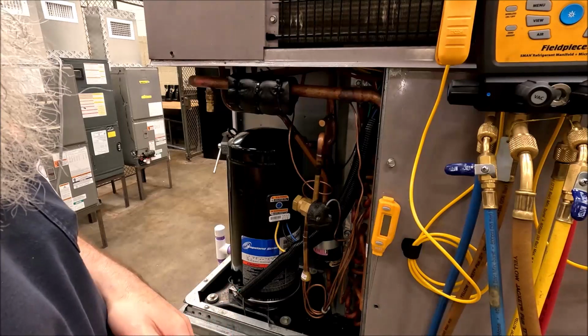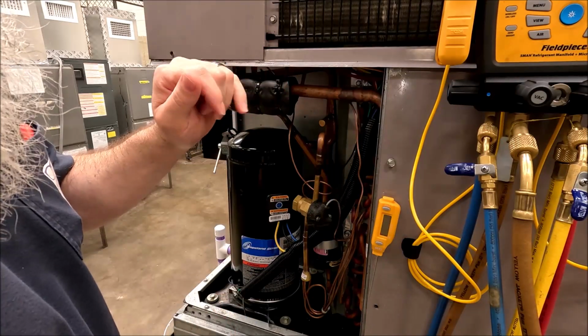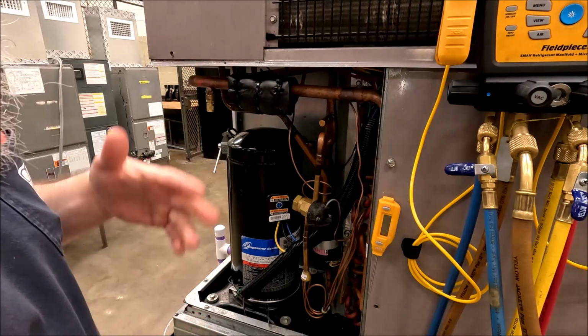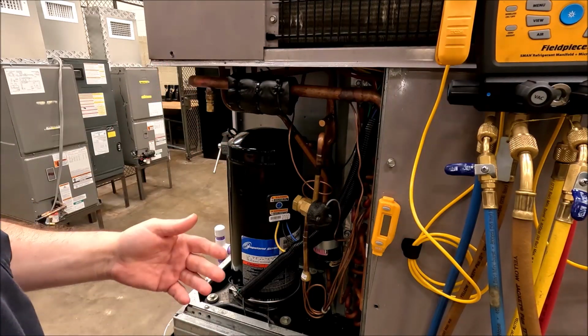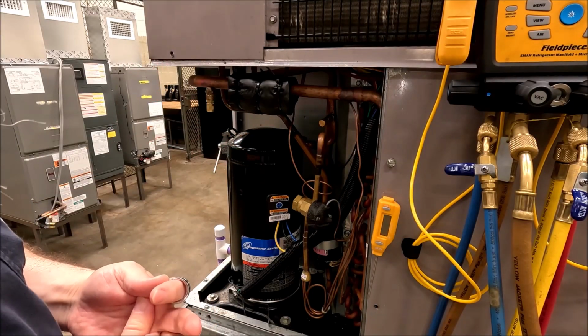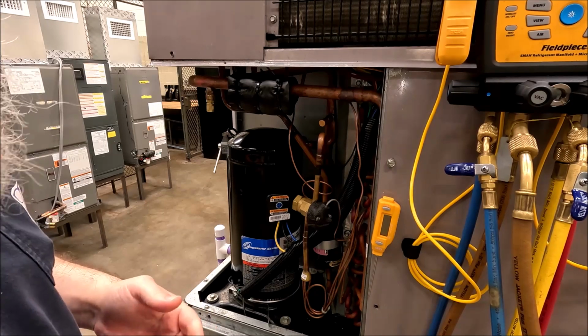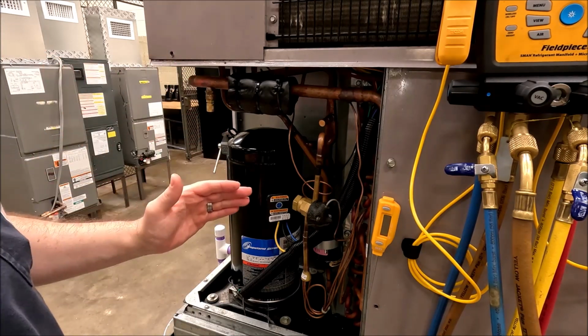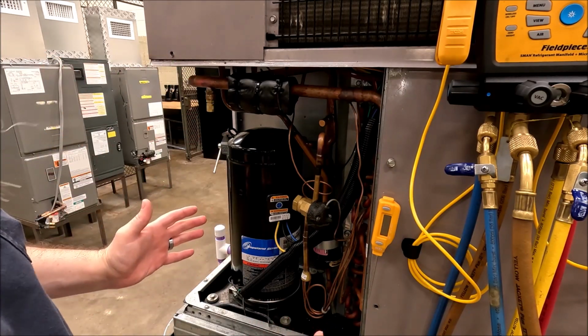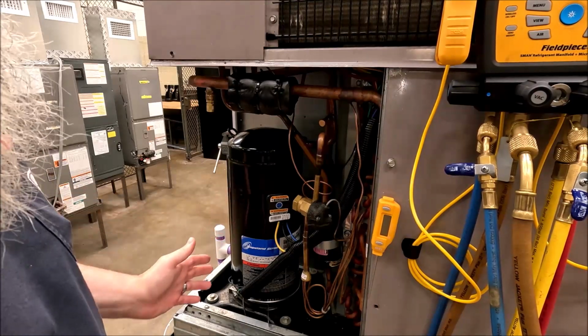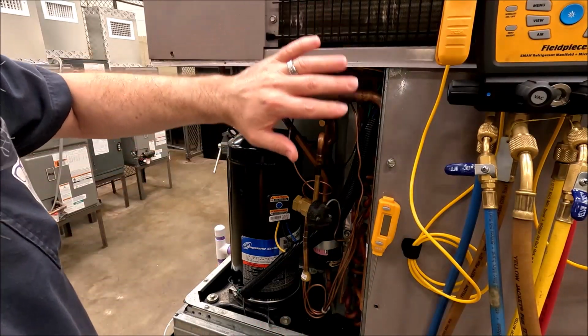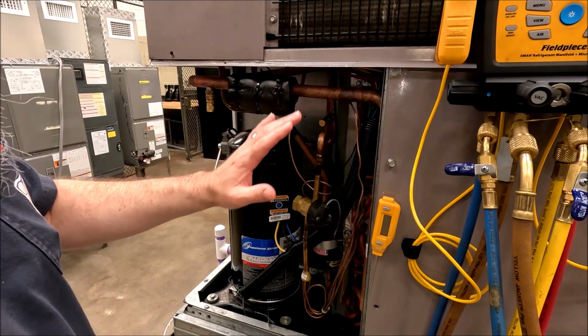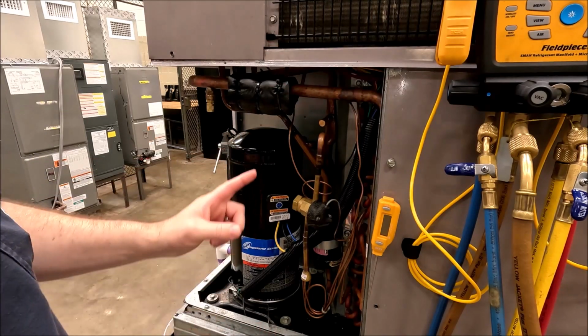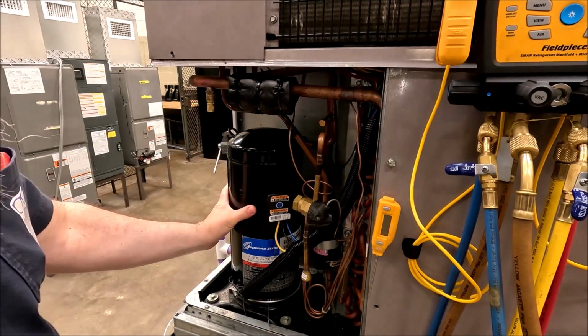But this time I'm going to use the digital set of gauges, a digital manifold. It's going to be the Fieldpiece SMAN. A lot of guys like this. I get some new guys that they just don't understand how to read it. So once again, as you're looking in this area, I know my compressor's here, and there's no obvious pressure taps on the outside for me to get to, so you have to take this cover off. And right away, I see a compressor.